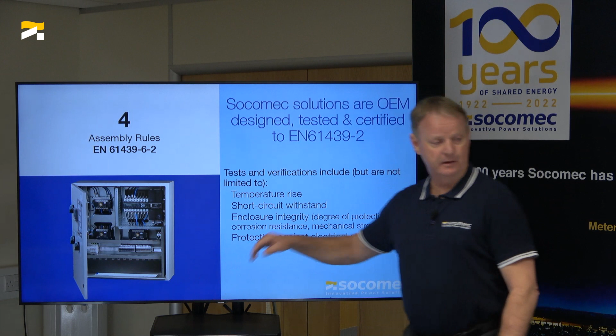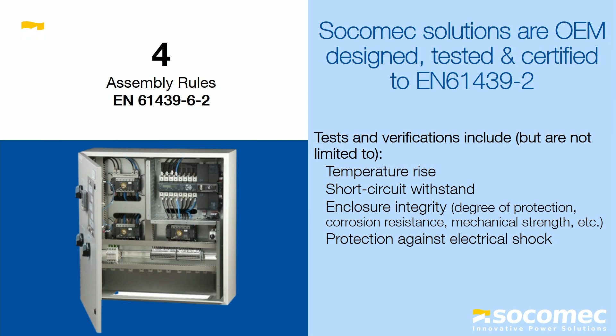Short circuit withstand, for ATSs, is very critical, whether they can withstand a short circuit to allow the upstream device to do its job. Enclosure integrity is about protection and resistance, but it can also be about whether you could put your finger in, or whether the door can be open when it's live, etc.